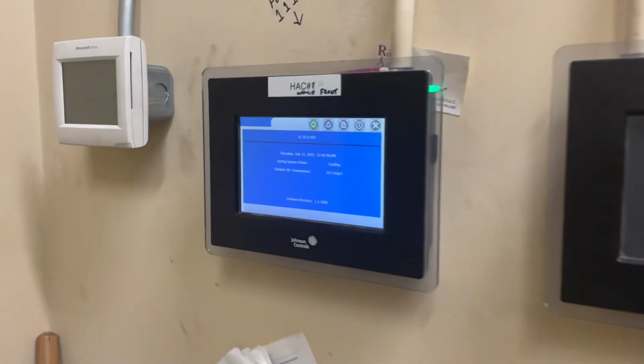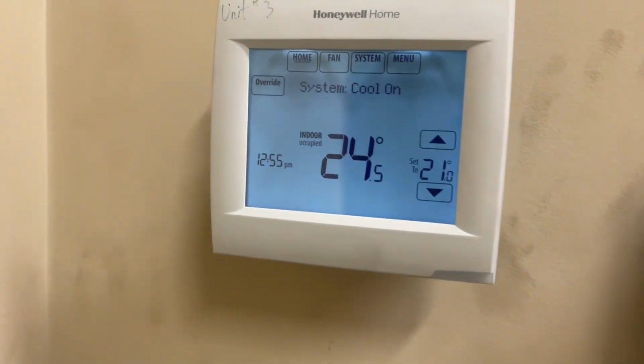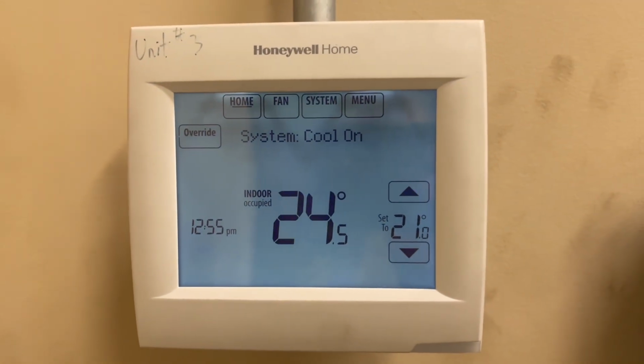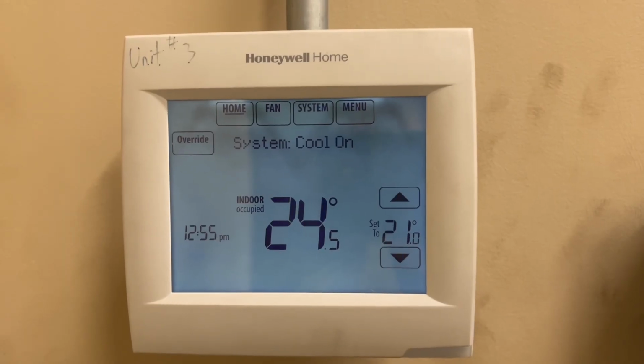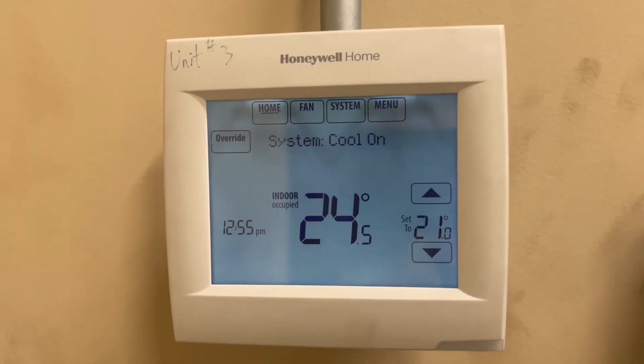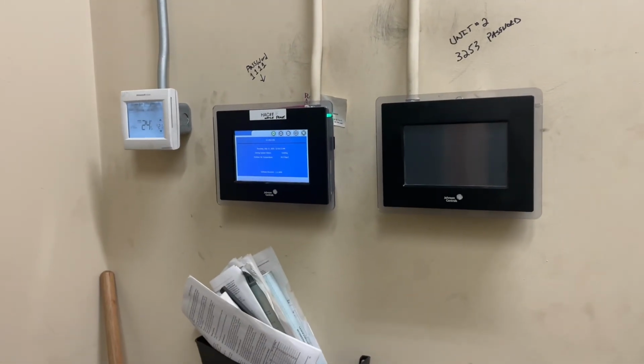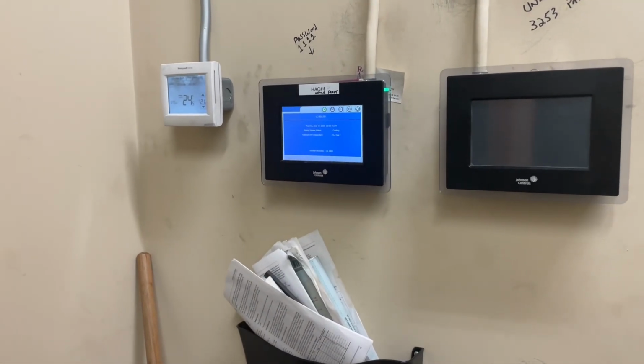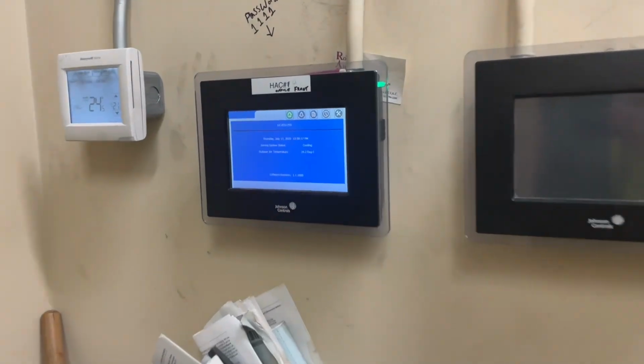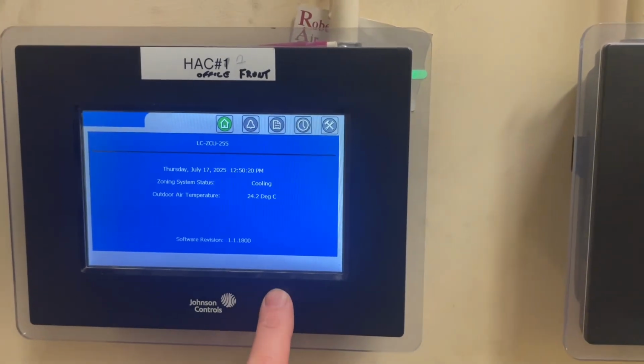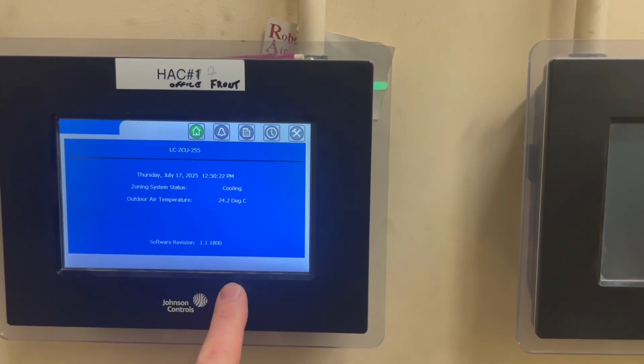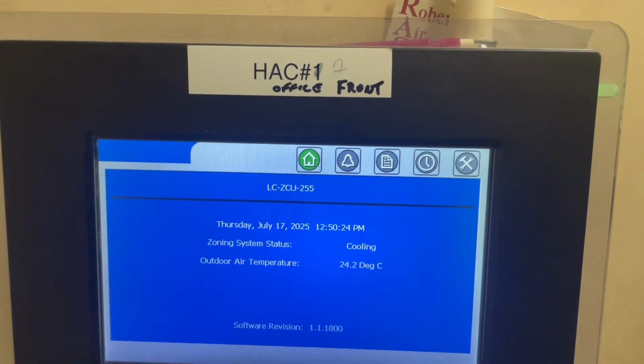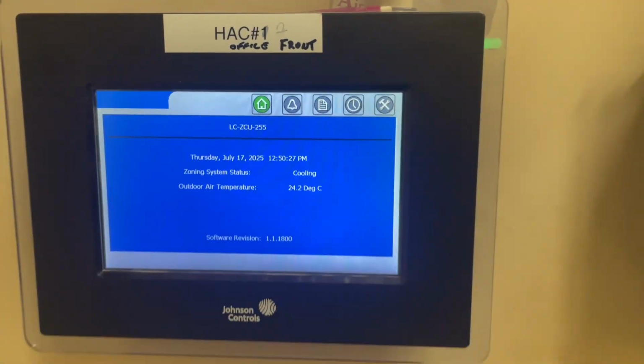All right, what do we have here? This is our thermostat. Yep, we're set to 21, it's 24 and a half inside temperature. If you're wondering why this controller is in this electrical room closet, it's because it has zone sensors throughout the change room and locker room space. All the rooftops here used to be off of these Johnson controllers here. I think they only have one now, which is what, HVAC 2 or 1 front office, but we're not dealing with this. This has no problems, and this one's been decommissioned. So we're looking at this here.